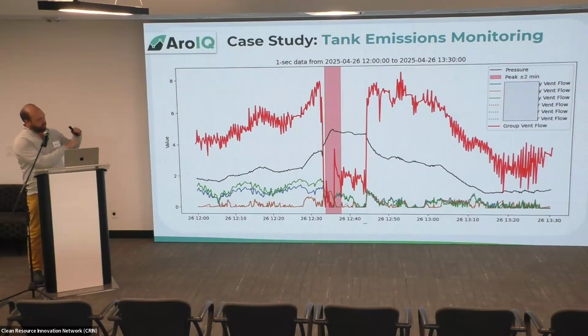As we removed data points or SCADA tags out of our analysis, we were still able to, with very high accuracy, continue to detect those events, whether a reseal problem, a full release, or a leak approaching that point event. So the point is we didn't actually need as many SCADA tags as people might have thought. They didn't need to install new ones—we could infer through correlation events on location, and then look backwards or upstream to figure out what caused it.